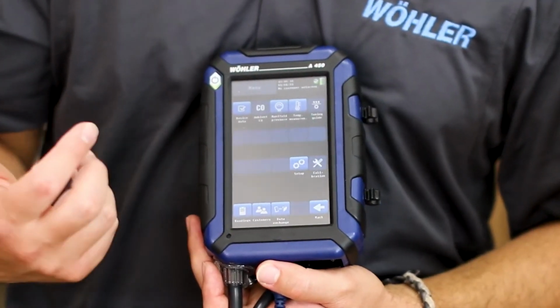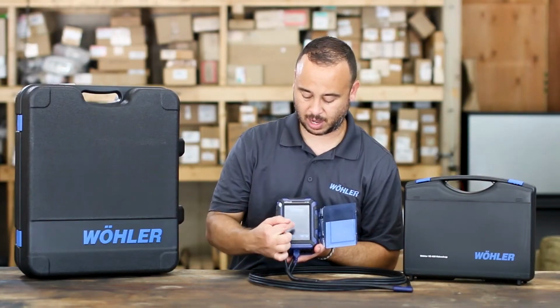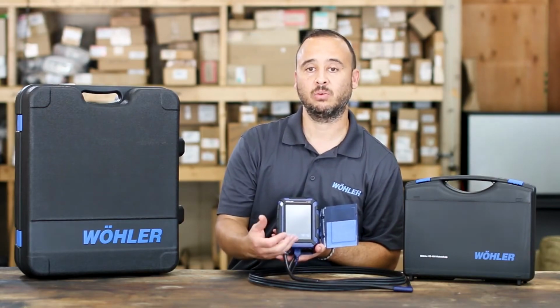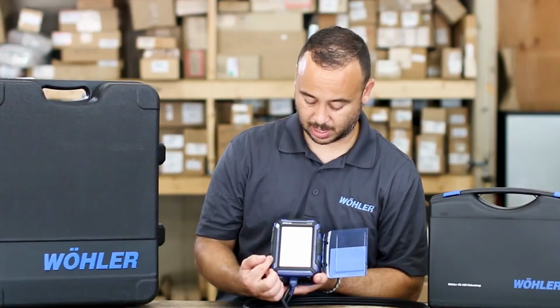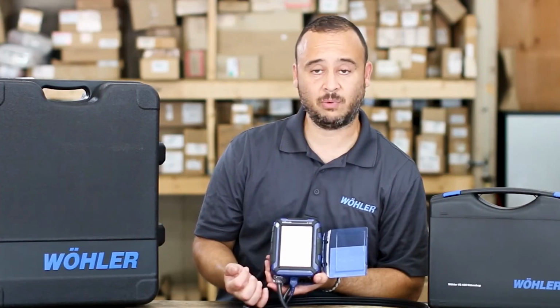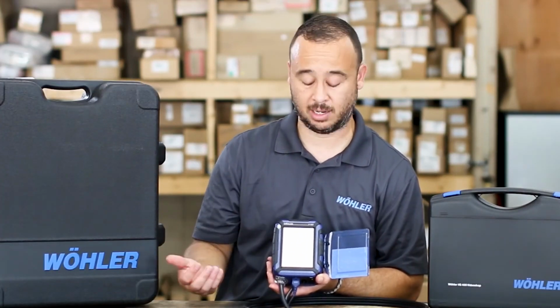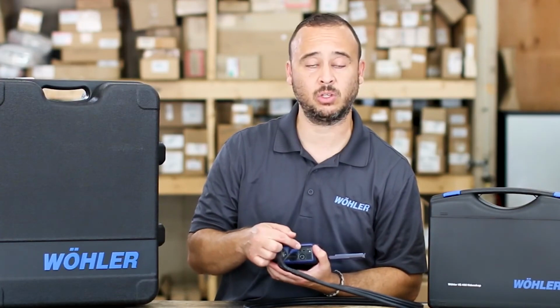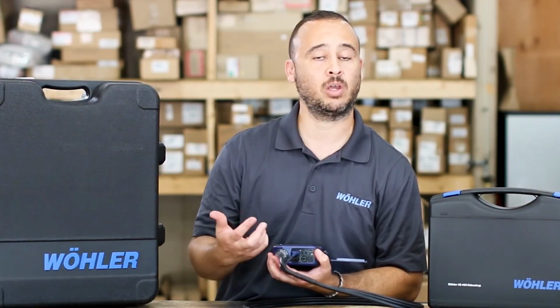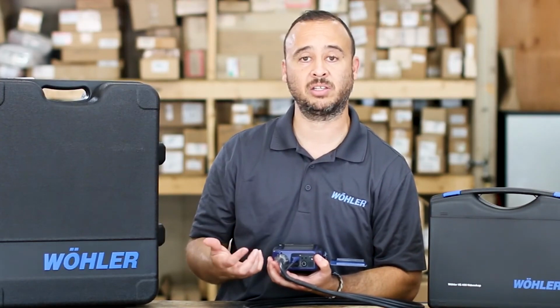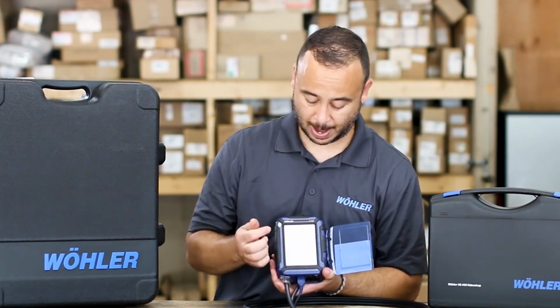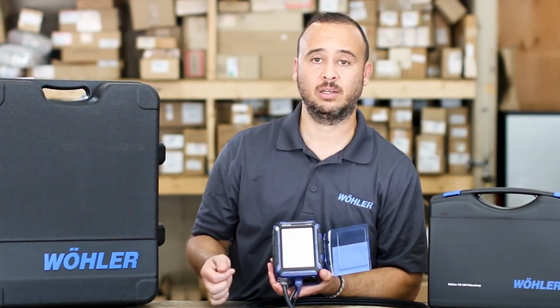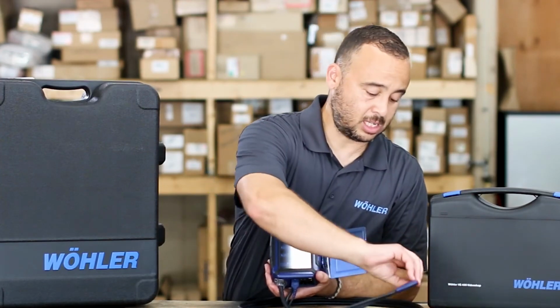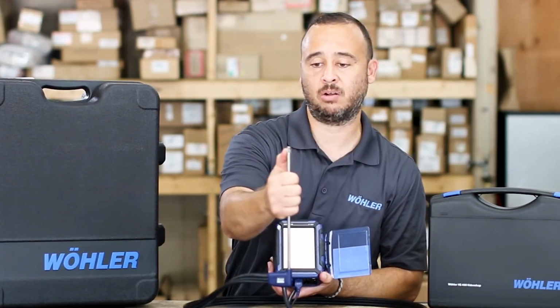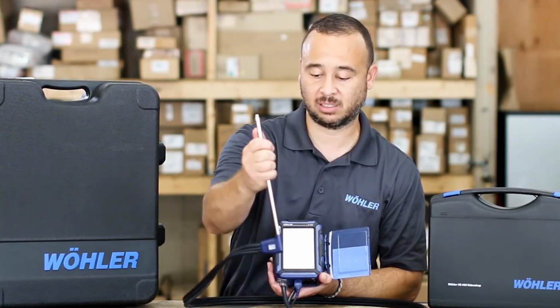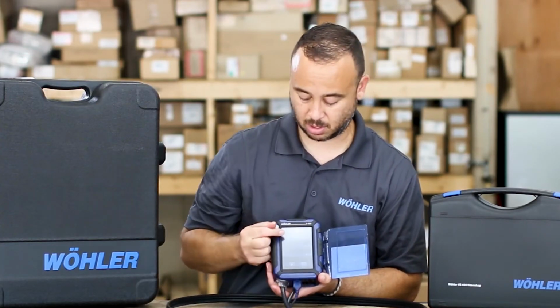Here you press the manifold pressure test, and it'll begin to graph once you have a hose hooked up, reading vacuum or lack thereof. On the very bottom, there is the TA reading, which is the ambient temperature we're reading outside. You can hook a K-type clip into the unit on the bottom for an external temperature probe, which we offer as an option on upper model kits or as an accessory on its own. The top side is your temperature stack, or the stack temperature of the unit. That temperature probe is located inside the gas probe itself in a bimetal configuration that sends a signal to the unit and displays temperature on the screen.